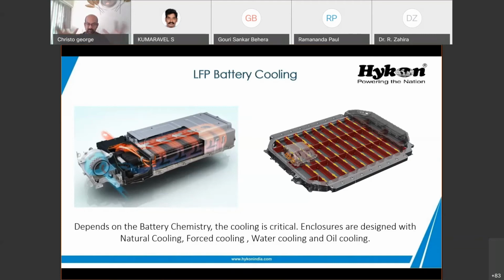You may need a blower, like in UPS inverters, where you need a blower to cool the MOSFETs and heat sinks, or like in a computer where the temperature has to be brought down - we call that forced cooling. Sometimes even air is not sufficient, so you need water cooling or oil cooling. The more you cool the cells, the better life of the cell you will get. If you look at a Tesla car, the cooling system is so perfect that the temperature will not rise more than 30 to 40 degrees inside the battery pack, so the life of the battery increases because life depends on temperature.